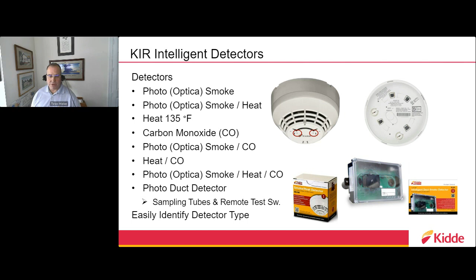It's nothing more than taking a screwdriver and actually turning the two different dials to the positions that you need for actually field addressing the devices. And then to move on there, we also offer a plethora of bases. We have sounder bases, which are very unique and important to the multifamily space, but also we have isolator bases, bases that have relays on them, so you can actually control something like a smoke damper from a detector. Standard bases, and they can come with skirts, or you can also add the trim skirt to them.